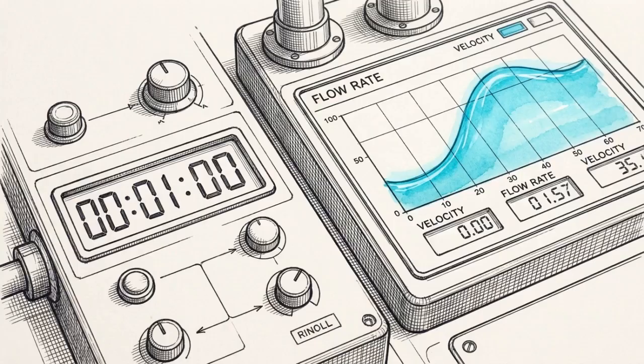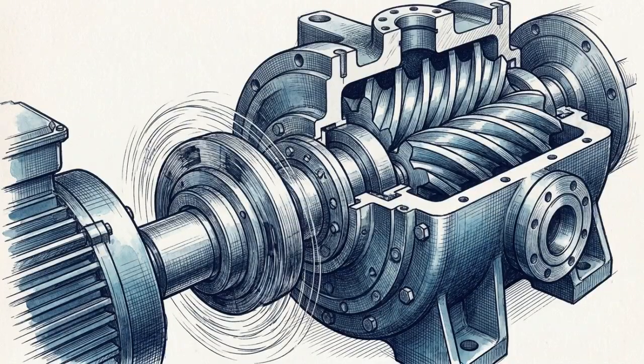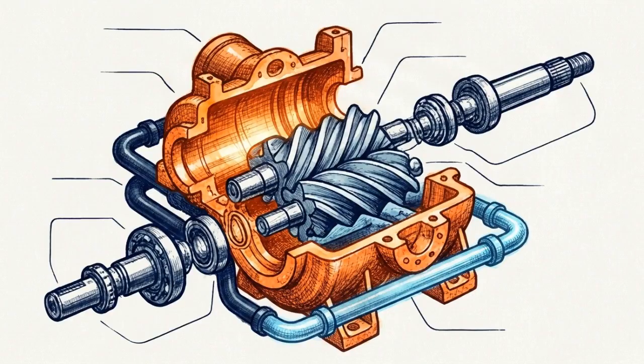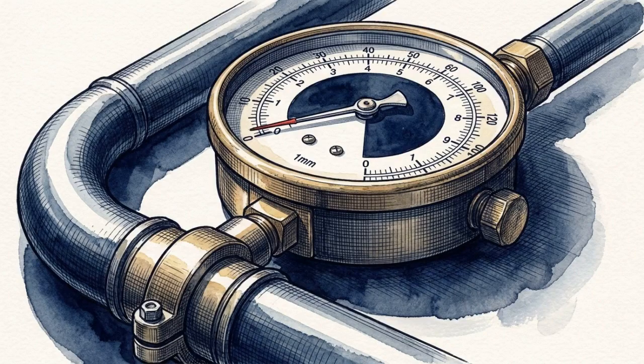At 60 seconds, hydronic flow is proven. The control system sends the final command, and the first compressors begin to spin. Even though the compressor motor is drawing current and rotating, the thermodynamic cycle is just beginning. The actual cooling duty being absorbed by the refrigerant is still negligible.